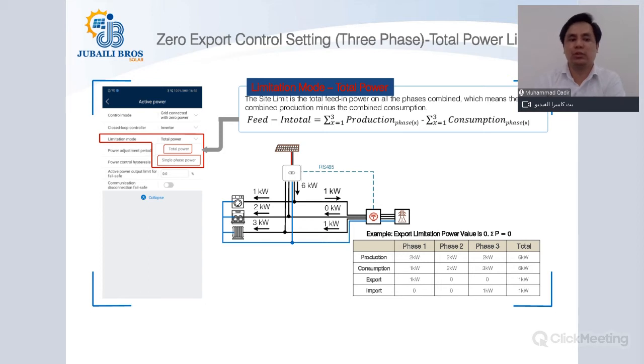After you have chosen the grid type point control as zero export and your right closed loop controller, the next option that you will have is the limitation mode. What limitation mode do you want to apply? Is it based on the total power or the single phase power? Now we will speak on this slide about the total power.